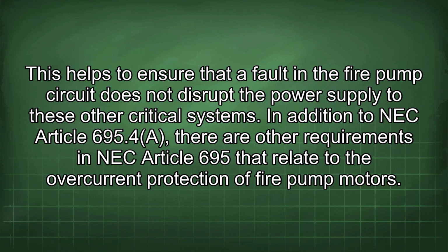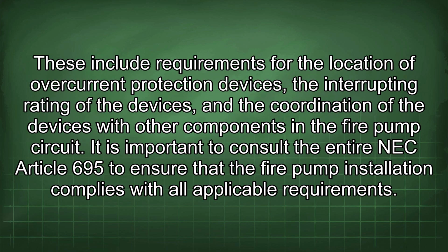In addition to NEC Article 695.4(A), there are other requirements in NEC Article 695 that relate to the overcurrent protection of fire pump motors. These include requirements for the location of overcurrent protection devices, the interrupting rating of the devices, and the coordination of the devices with other components in the fire pump circuit. It is important to consult the entire NEC Article 695 to ensure that the fire pump installation complies with all applicable requirements.